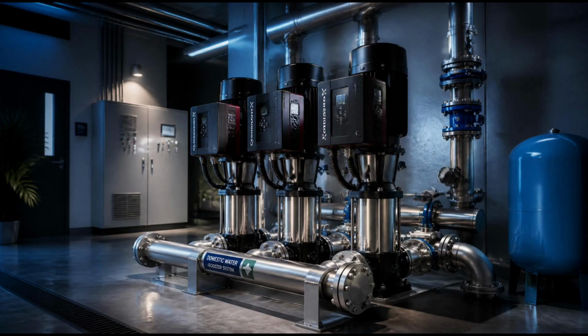But regulation alone is not always enough. In tall buildings, those rising many stories above street level, there is another challenge that pressure regulators cannot solve on their own. Water is heavy, and lifting it against gravity requires energy. Every 10 feet of vertical rise reduces pressure by a little over 4 pounds per square inch. In a building of 20 or 30 stories, that loss accumulates quickly. Water that arrives at street level with perfectly adequate pressure may barely trickle from a faucet on the upper floors if nothing is done to compensate.